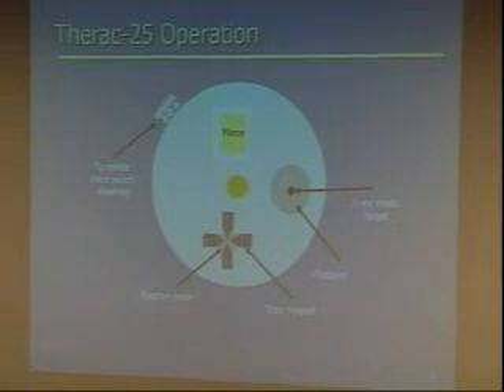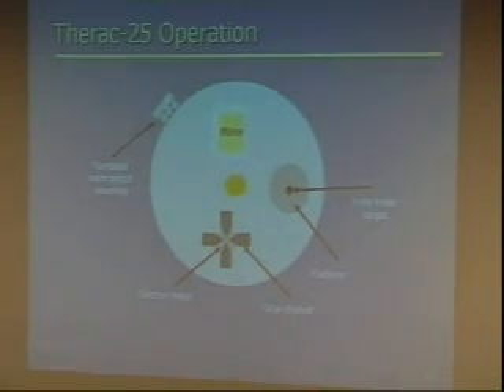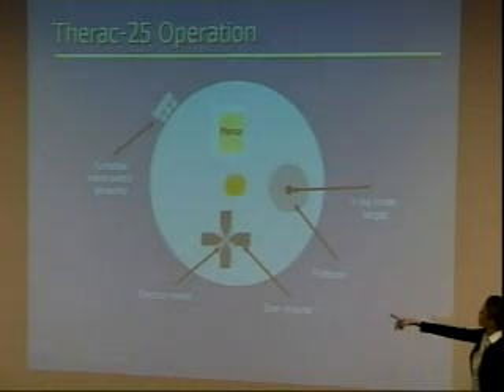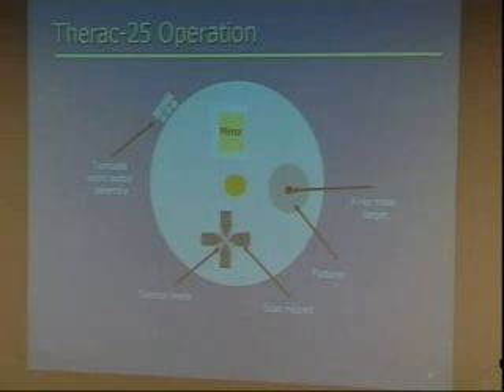So just a brief explanation of the structure of the Therac-25. There is a turntable in this machine, which was the reason for most of the failures of the system. The rotation of this turntable puts different equipment in the beam path, which produces the 2 modes, the electron mode and the X-ray mode. The position of this turntable is controlled by 3 microswitches. These microswitches define which equipment should be in the beam path in order to produce the X-ray or the electron mode.